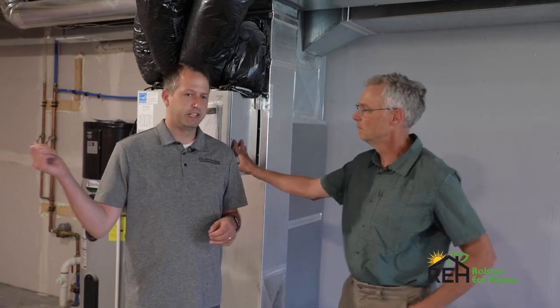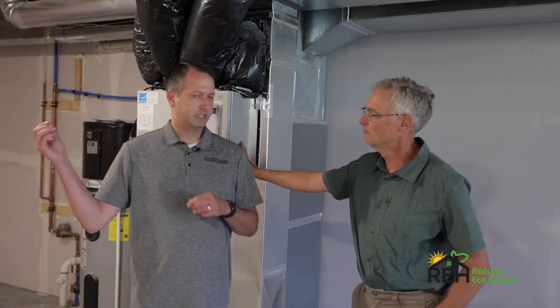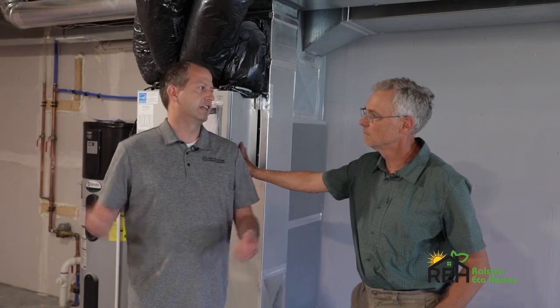What is commissioning and why do we do commissioning? Sure. Commissioning is the last step in making the system perform the way that it's designed to operate. Items like airflow, making sure the airflow is correct, making sure refrigerant charge is properly done so that the right amount of BTUs are put into the airstream. And then the last step is balancing, moving the air from the ductwork system to the parts of the house that you need the heating and cooling.